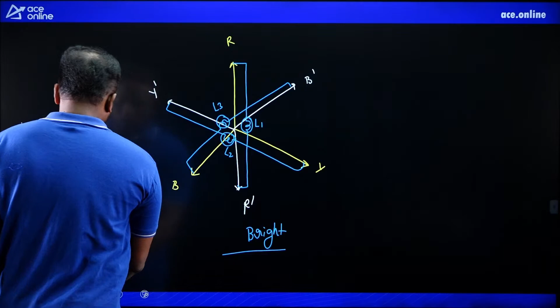Let me take another diagram. This is R, Y, B, the bus bar's 3 phases, and the alternator's 3 phases. At one instant, suppose we get R dash, Y dash, B dash positioned like this. Now L1 is connected between R and R dash, L2 between Y and Y dash, L3 between B and B dash. This is how the lamps are connected.